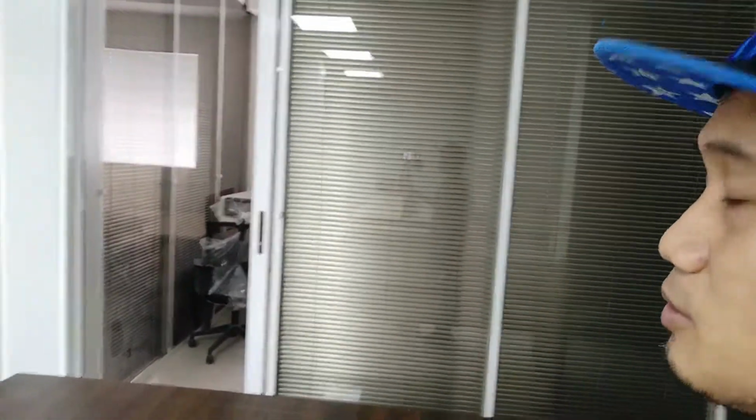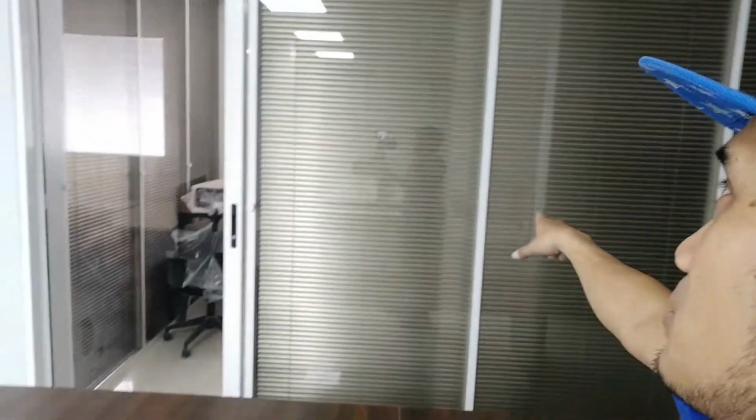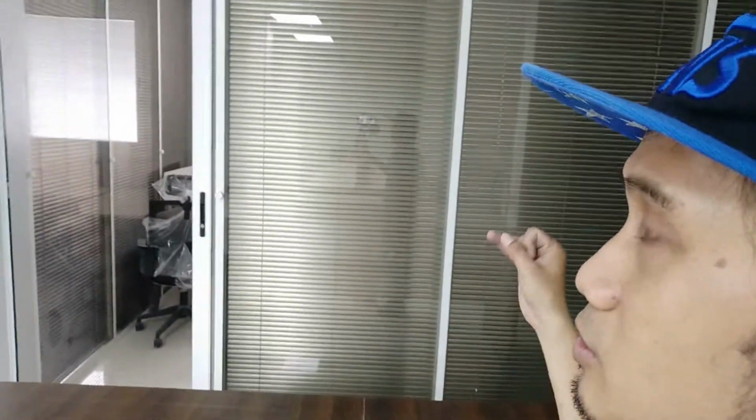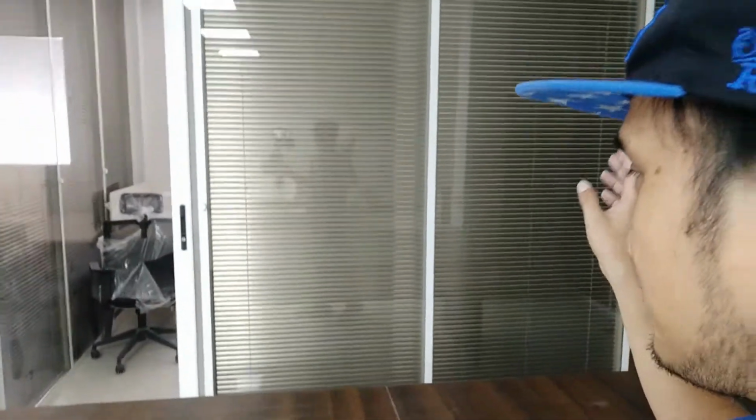Okay, and we have also here another room. This area here is not the original plan that we knew before. The original plan is we only have two rooms here. This room is divided into two, but they changed it to make it one. So we have cables here. We run the cables, 4 cables here. It's 2 for voice and 2 for data, because the plan is we have 2 workstations here. So we run the 4 cables, so that's why.